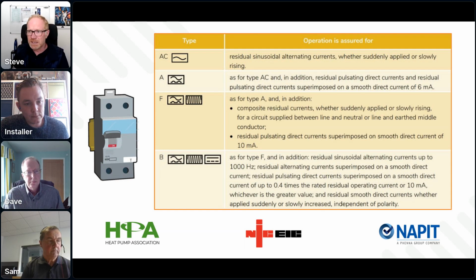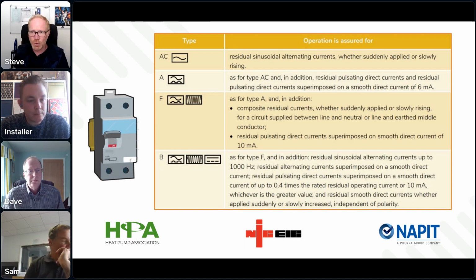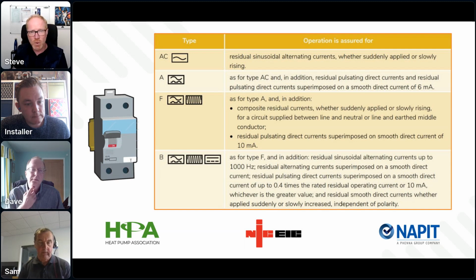And another reason is that many heat pumps, as I just said, do not produce smooth DC residual current anyway. So a standard heat pump with single phase compressors, without that complex electronics I talked about, might only generate AC or pulsating DC. So in that case, we have seen heat pumps where a type A will be absolutely fine. As they become more modern, more complex, better, more efficient, we're seeing more of those electronics and drives that are becoming more complex. So, there might be historic reasons for that.